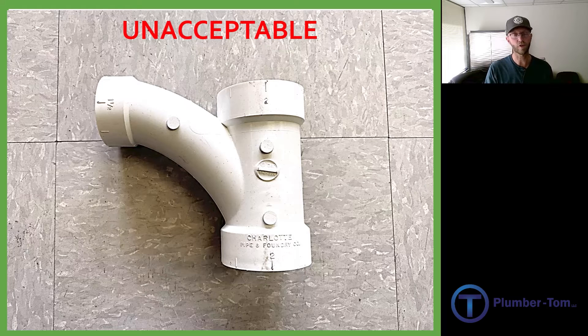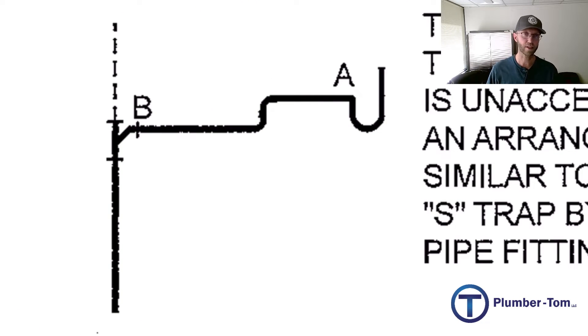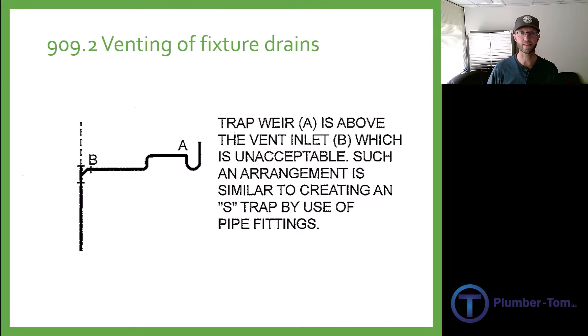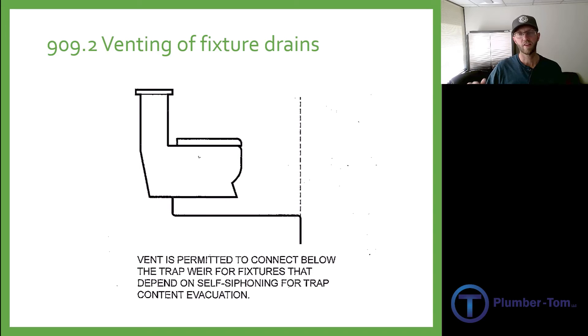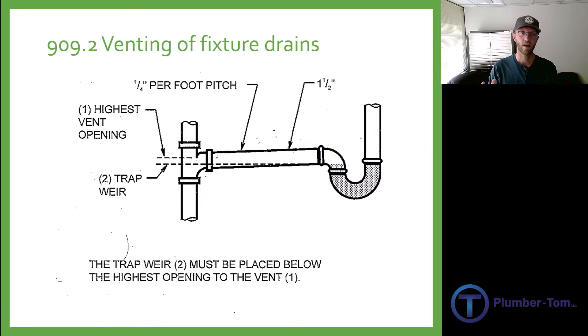That is why we use sanitary tees in a vertical position. Here's another thing that we do not do: you can see on the left we've branched off for our fixture coming towards the trap, but then offset up. This has created an S-trap. It loses the vent and this is not an acceptable way to run pipes as we're coming over to a trap. It has to come even and flat over to the trap so that the trap has access to the airflow in the vent. Toilets are a little different — the liquid seal and the trap are in the fixture and well above where the vent connects. But because a toilet self-siphons and refills itself, as long as that pipe has airflow and a vent, it will be fine. sanitary tees are good because they give us that open airflow and space, not restricted by the long sweep of other connection fittings.